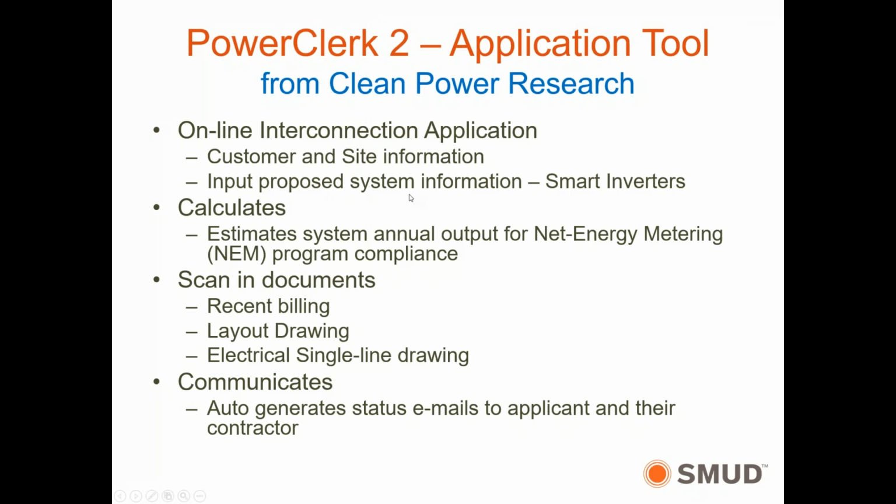One of the cool things about it is a pull-down list that only includes the smart inverters that are approved for installation in the state of California. And it coincides with SMUD's approved list. That gets us the smart inverters that have passed IEEE 1547 and tested to UL 1741 SA. And that eliminates a lot of worries. We just go ahead and hook those up.